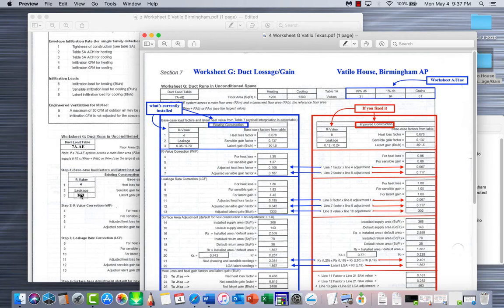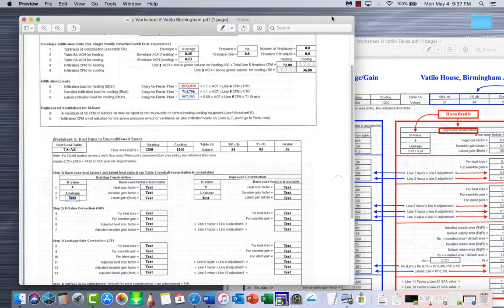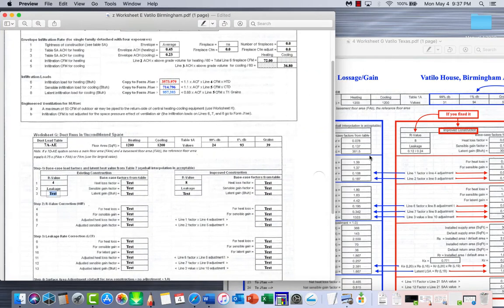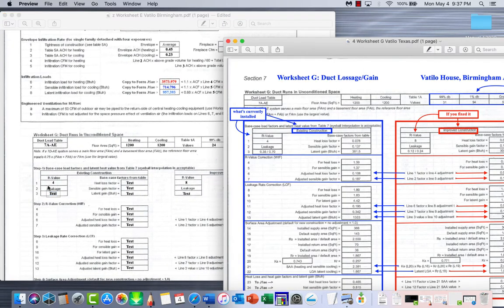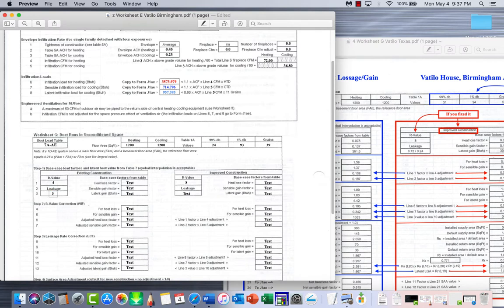The first part is construction information. Our construction was R4 insulation as shown on the survey. For the current leakage on the supply and return: 0.35 and 0.70. For the adjusted improved construction - if we seal it up with R8 - those values become 0.12 and 0.24. Let's put those numbers in on both sides of the worksheet.